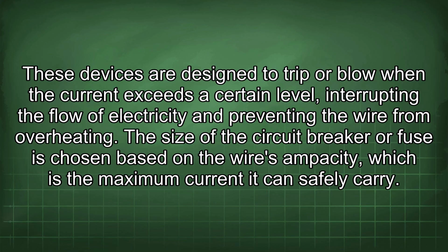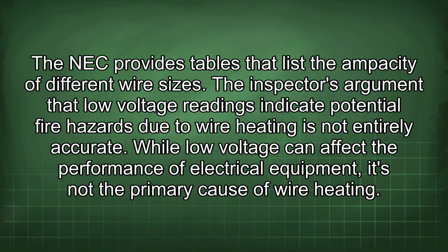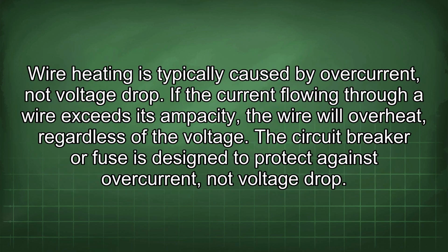The size of the circuit breaker or fuse is chosen based on the wire's ampacity, which is the maximum current it can safely carry. The NEC provides tables that list the ampacity of different wire sizes. The inspector's argument that low voltage readings indicate potential fire hazards due to wire heating is not entirely accurate. While low voltage can affect the performance of electrical equipment, it's not the primary cause of wire heating. Wire heating is typically caused by overcurrent, not voltage drop. If the current flowing through a wire exceeds its ampacity, the wire will overheat, regardless of the voltage.